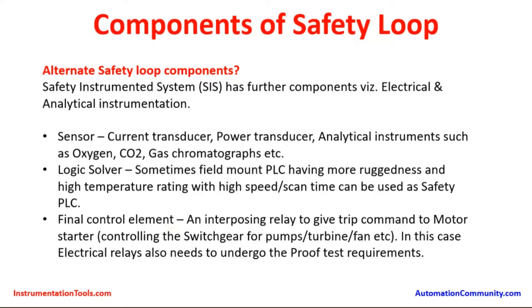For the final control elements in an electrical interface, there is an interposing relay to give a trip command to a motor starter. A motor starter is an electrical device — a controlling switchgear for pumps, turbines, fans, etc. Electrical relays also need to undergo proof test requirements. The interposing relays are mostly located in the switchgear control room in a separate electronic cabinet, taking input from the SIS logic solver and giving a command to trip the switchgear for pumps, turbines, fans, etc.